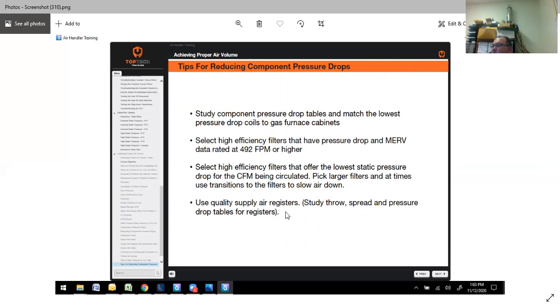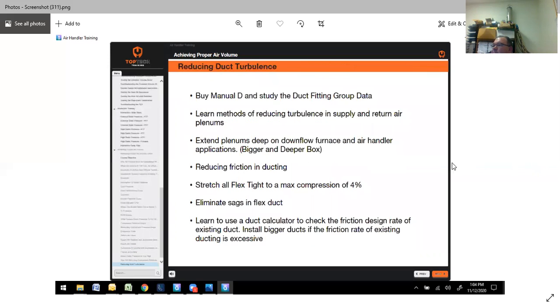Use quality supply air registers. In some cases, it's there in the house. You can't really do anything about it. But if you're starting from scratch, use the proper supply air registers. Buy Manual D and study the duct fitting group data. Learn duct layout, and as you come across things, you'll start to see mistakes and issues from previous installations and ways to resolve that.